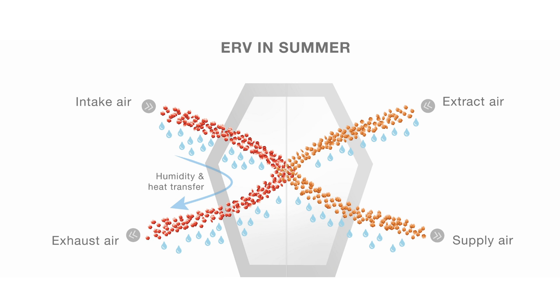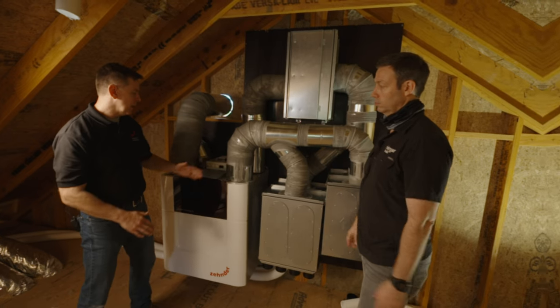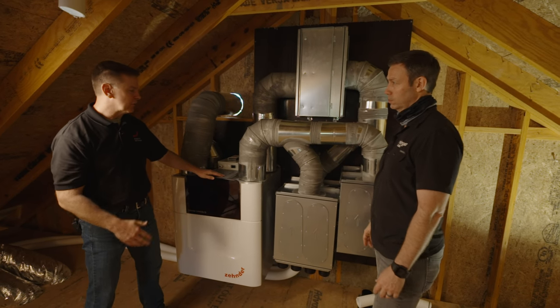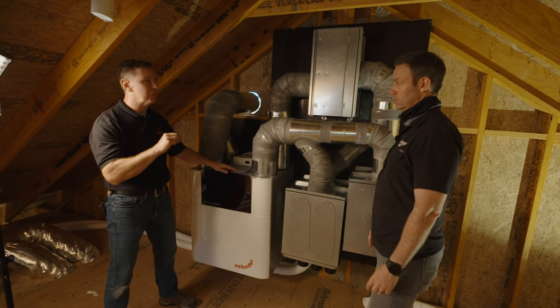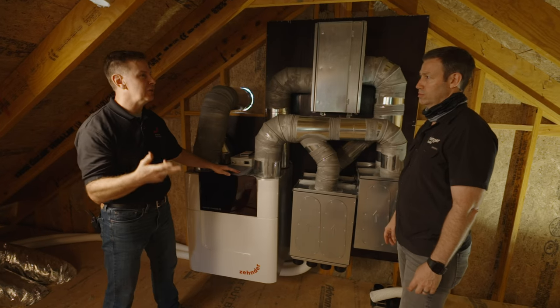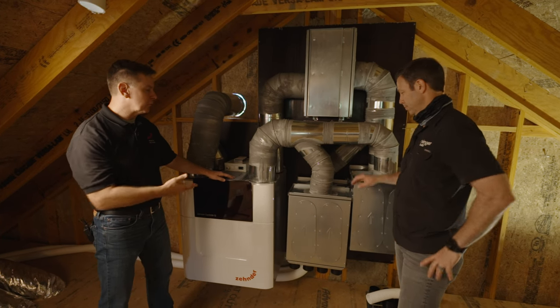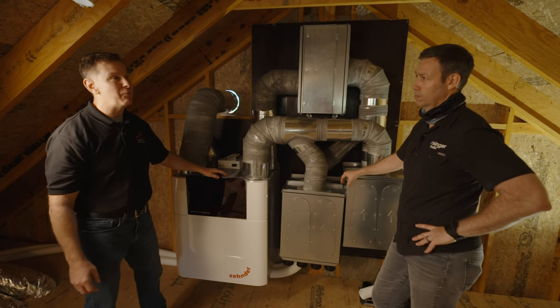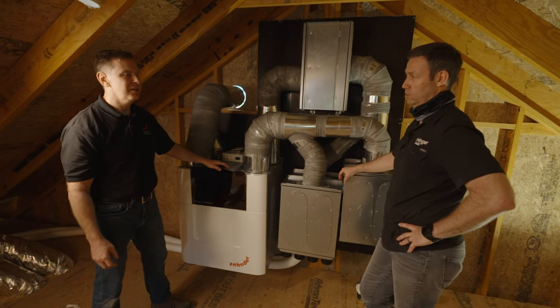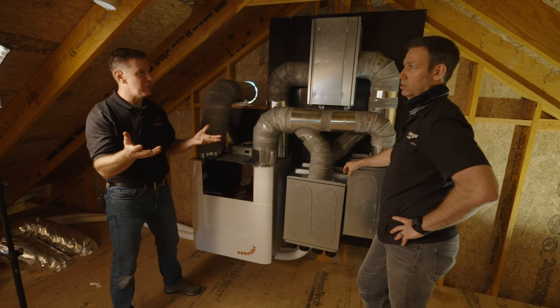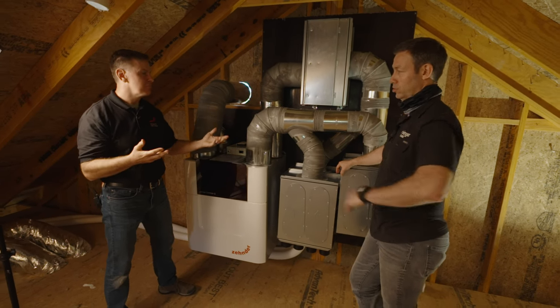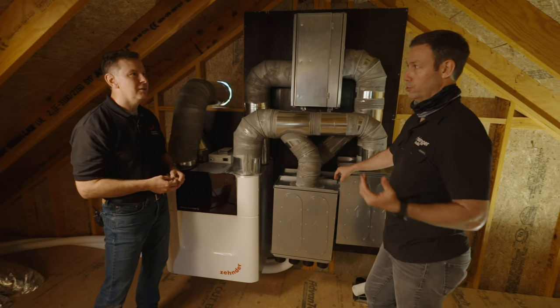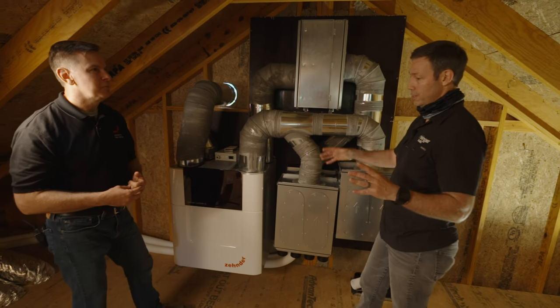And how efficient is this in both heat recovery and moisture recovery? With an ERV, you're going to have a slightly less sensible, or heating, recovery than you do with an HRV. But still, you're going to be with this unit around 85% heat recovery. That's amazing, that's 85% of the difference in temperature between outdoors and indoors. Gotcha, so it's a 50 degree delta, which would be unusual for me. Yeah, but a 50 degree delta, yep.